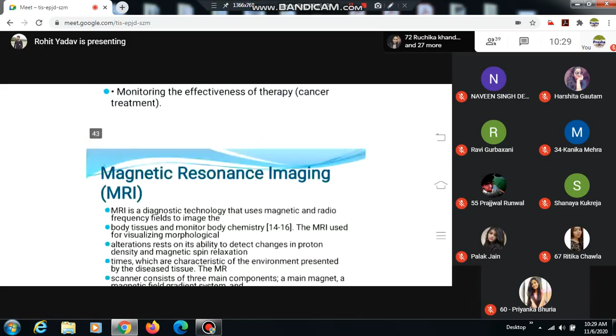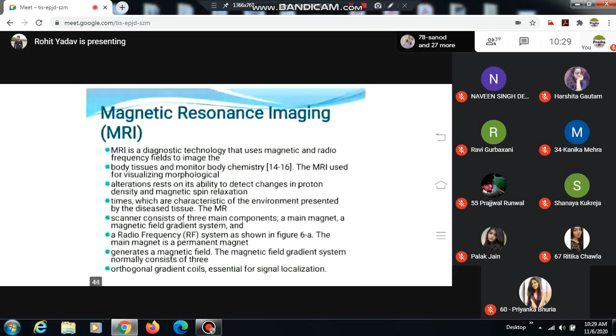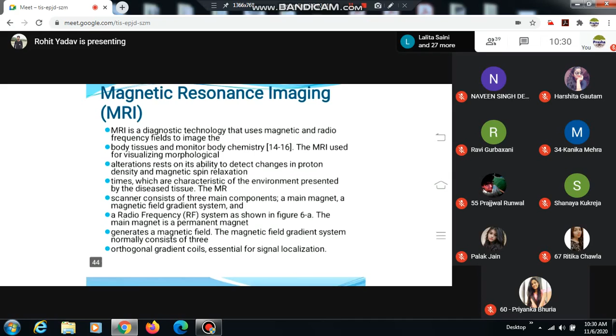Then magnetic resonance imaging, MRI. MRI is a diagnostic technology that uses magnetic and radio frequency fields to image body tissue and monitor body chemistry. The MRI's use for visualizing morphological alteration rests on its ability to detect changes in proton density and magnetic spin relaxation times, which are characteristic of the environment presented by the diseased tissue. The MR scanner consists of three main components: a radio frequency system, the magnetic field, and the magnetic gradient system, which normally consists of three orthogonal gradient coils, essential for signal localization.